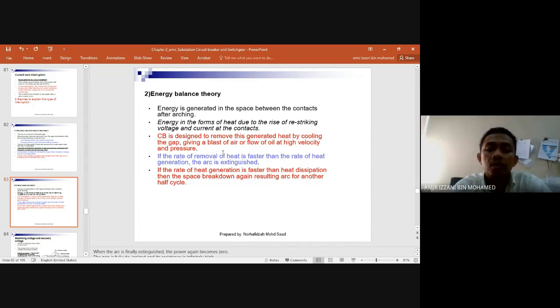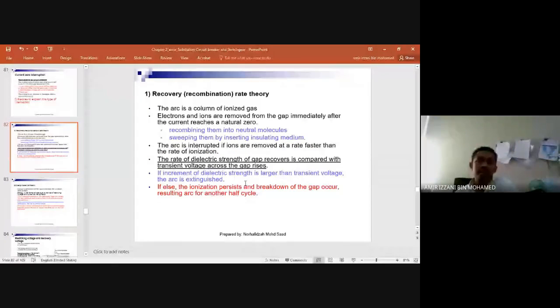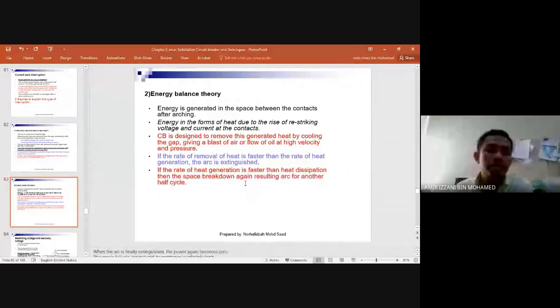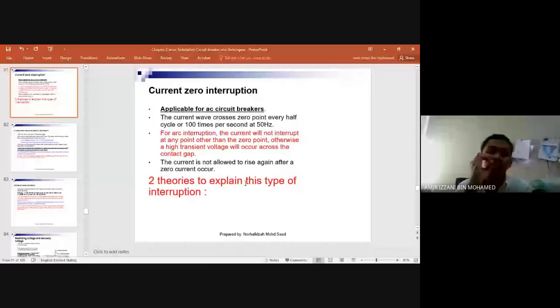Okay, if the rate of removal of heat is faster than the rate of heat generation, then the arc can be extinguished. So we need to cool down the contact as fast as possible, so that the arc can be extinguished. If the rate of heat generation is faster than heat dissipation, then the breakdown or the generation of arc will occur again. So in these two theories, the recovery rate theory and energy balance theory, it only works during zero current and zero voltage.